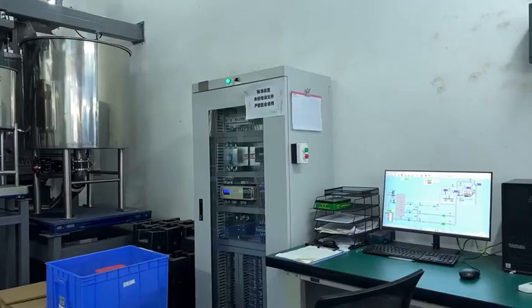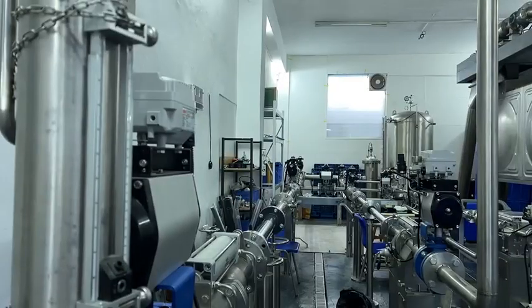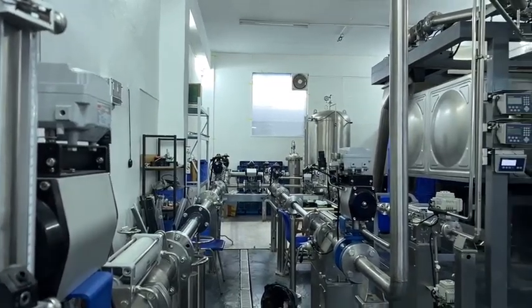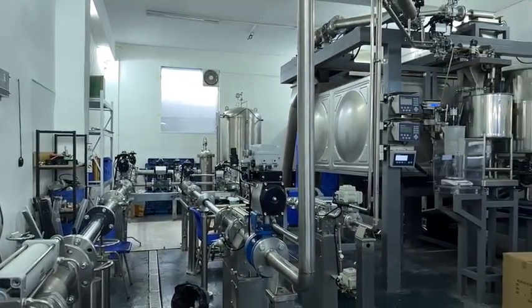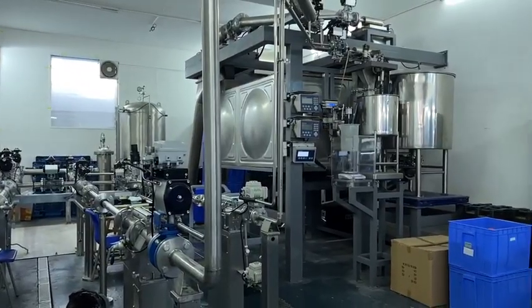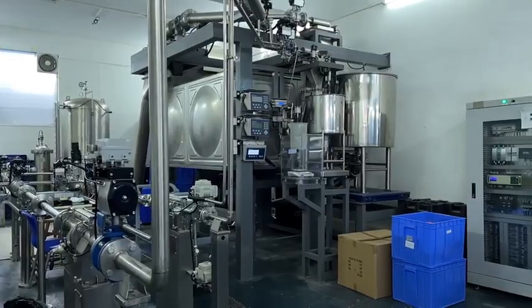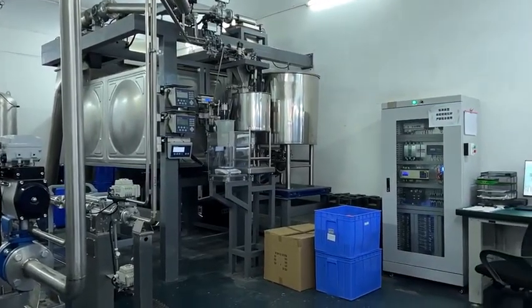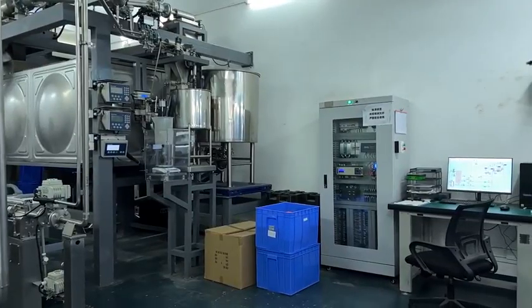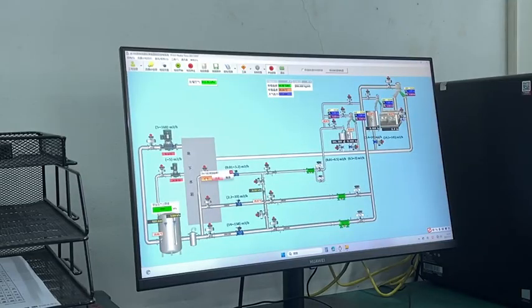The calibration facility uses a closed-loop water circulation system with a stainless steel storage tank, variable speed pump, and a precision reference flow meter traceable to national standards. Flow rate, fluid temperature, and pipe pressure are all monitored continuously throughout each test. The calibration system is managed by a SCADA-controlled platform. The software displays the full loop schematic in real time, showing pump status, valve positions, flow direction, and live measurement data from every instrument on the line.